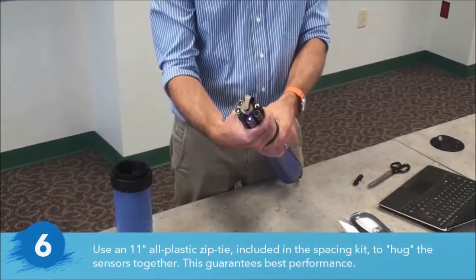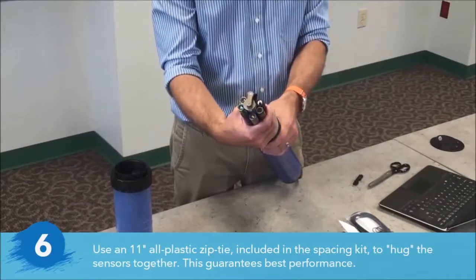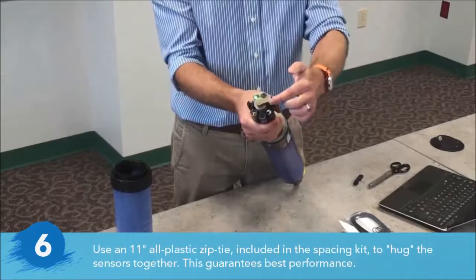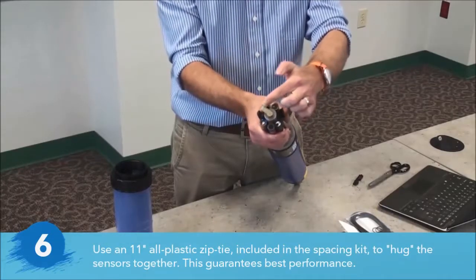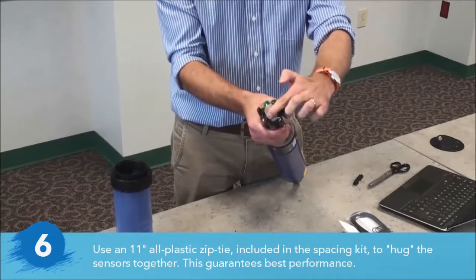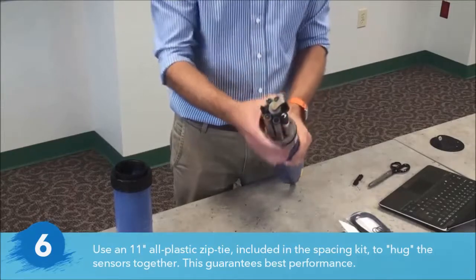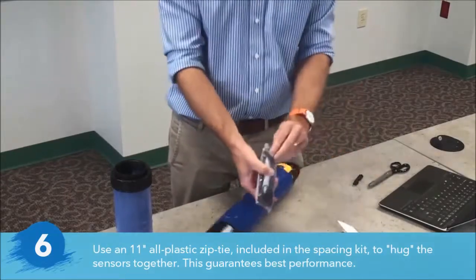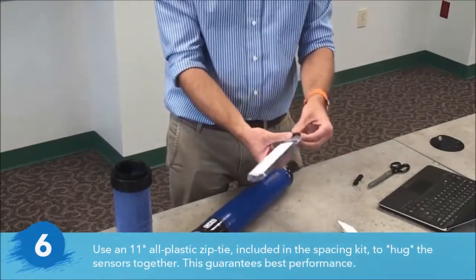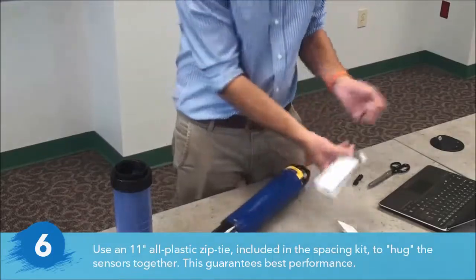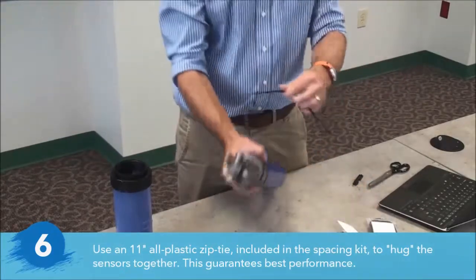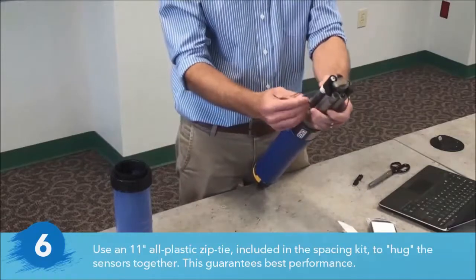The last step is to use a zip tie to actually hug the sensors to the central wiper. This allows optimal placement of the wiper brush and the CT channel. So we'll take a zip tie. Any 11-inch all-plastic zip tie will work. And we will install it around the sensors.